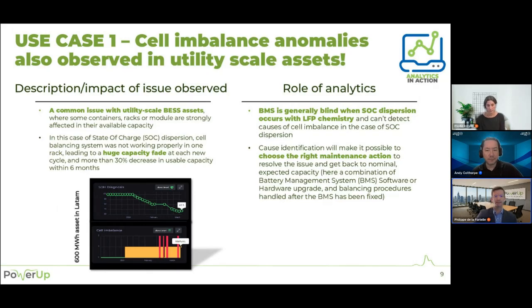Same cell imbalance root cause, and going deeper into what's really causing the problem, there could be different reasons: SOC dispersion (state of charge dispersion), capacity dispersion, or resistance dispersion. Each diagnosis leads to a different maintenance action. So it's really important to detect cell imbalance, but also to go straight to the precise diagnosis to know if the problem is recoverable, and if so, to recover part or all of the affected capacity. In this striking case, SOC dispersion was the root cause.